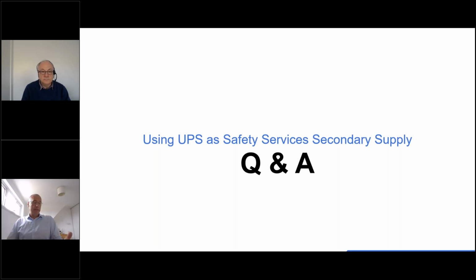So we're getting to the point where there are no secondary supplies. We're not allowed to put generators in for environmental reasons and things like that. So we have to do something, and a UPS can be used if we do it correctly, and it's very important that we do it correctly. So yes, we are trying to get the standards up to date, but in the meantime, we're trying to make sure it's done properly.